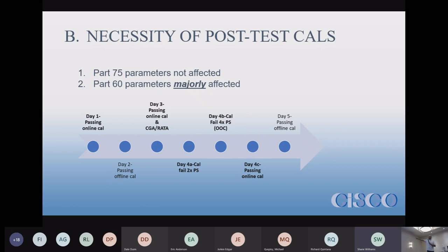Scenario 4B: you fail four times the performance test. What happened? And this is what Kevin was alluding to. The data becomes invalid backward for Part 60, which isn't a big deal if you're going back to simply the cal before, but if going backwards to that passing cal means you go through a CGA or a RATA, you're kind of screwed. So what we're recommending is, if you run a calibration right after that, specifically the RAD, while the source test is still there and you pass, everything's good. Even if you fail, they're still there and you don't have to redeploy them back to the site if you find out 2 days later, because you were down the next day and then you came back online.